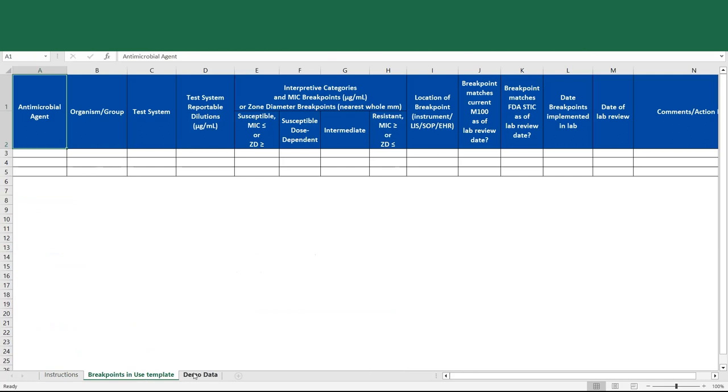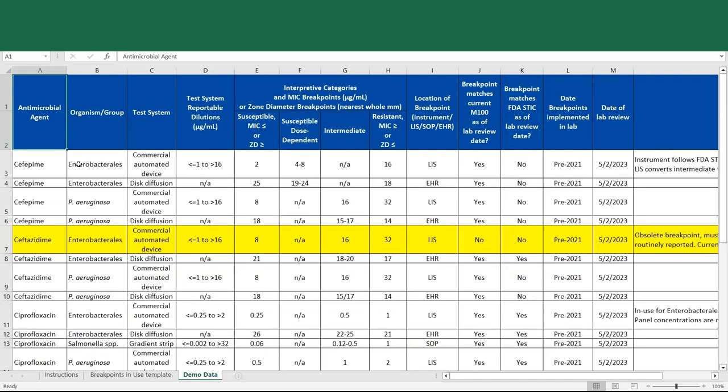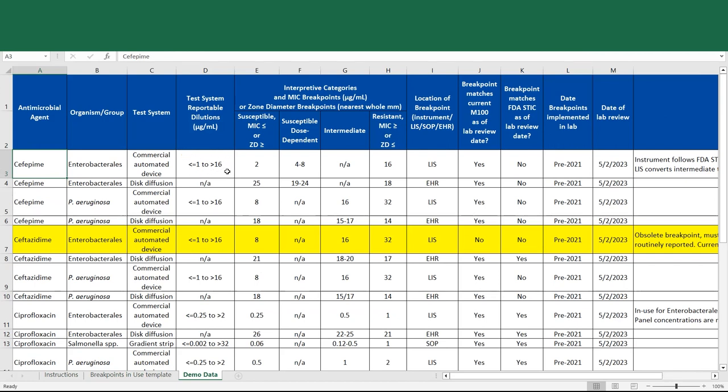To assist you in filling out the form, we've compiled a demo data sheet, which is already filled out with several examples. In the first example, we'll see cefepime Enterobacterales breakpoints as tested on a laboratory's commercial automated device. We see that the test system reportable dilutions is listed here, and this is something that's important for you to compile in order to determine whether updated breakpoints are able to be applied onto a commercial device.